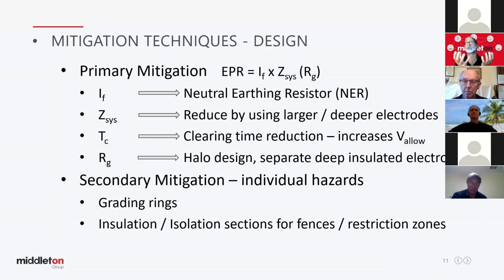So the pad mount's insulated. It's a separated design, meaning your HV earthing system, which is the framework of the pad mount and the electrode, is separate to your LV MEN system. That's separated. You've got to look at what the EPR will be, and have a look at your insulation levels in between your HV and your LV, your standoff insulators for your LV earthing bar and all these sorts of things. As I say, it becomes complex. But to answer your question, yeah, the whole substation is insulated from ground, and indeed the earth electrode as it enters the ground is insulated all the way down to the bare exposed earth electrode that's deep buried, potentially 20 metres, 30 metres in the ground.